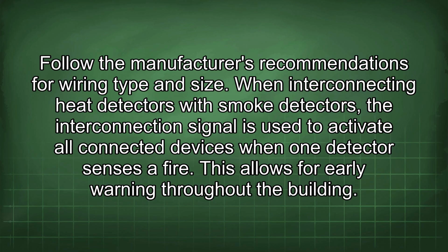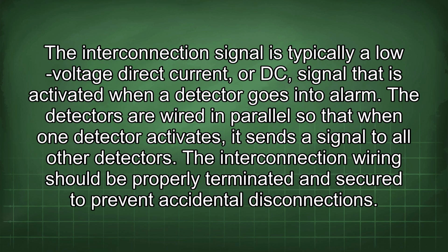When interconnecting heat detectors with smoke detectors, the interconnection signal is used to activate all connected devices when one detector senses a fire. This allows for early warning throughout the building. The interconnection signal is typically a low voltage direct current, or DC, signal that is activated when a detector goes into alarm. The detectors are wired in parallel so that when one detector activates, it sends a signal to all other detectors.